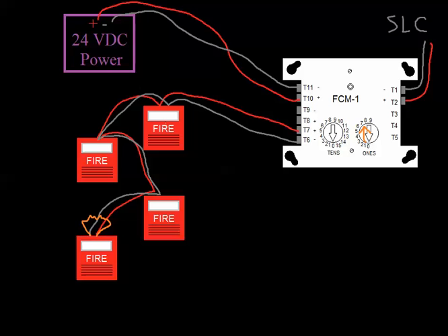At 24 volts, most of these horn strobes could run on 12 volts. So if you had a data circuit hooked up to it, even though there's not much power available, it's probably possible that they would maybe chirp a little or make some sort of noise. So the diode is blocking any current at all from passing through until that polarity reverses, and now it's taking this 24-volt power through and out to all these horn circuits.